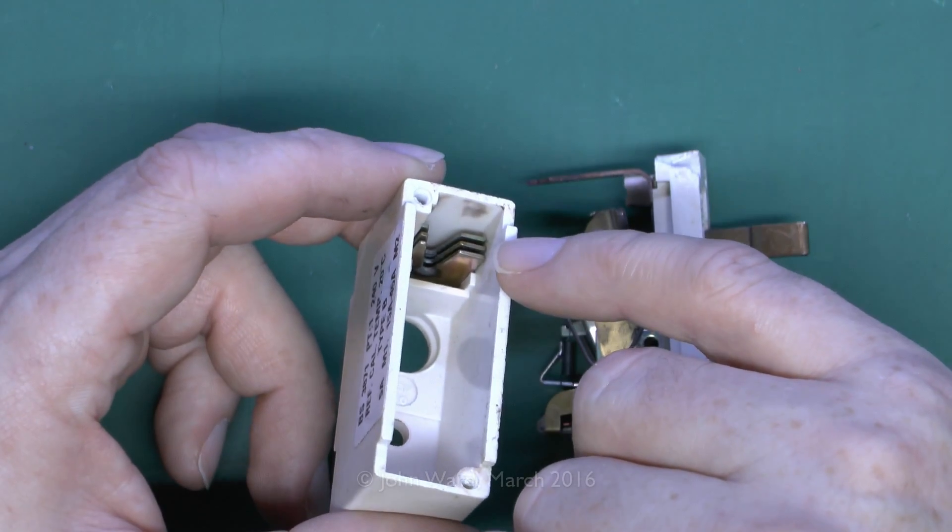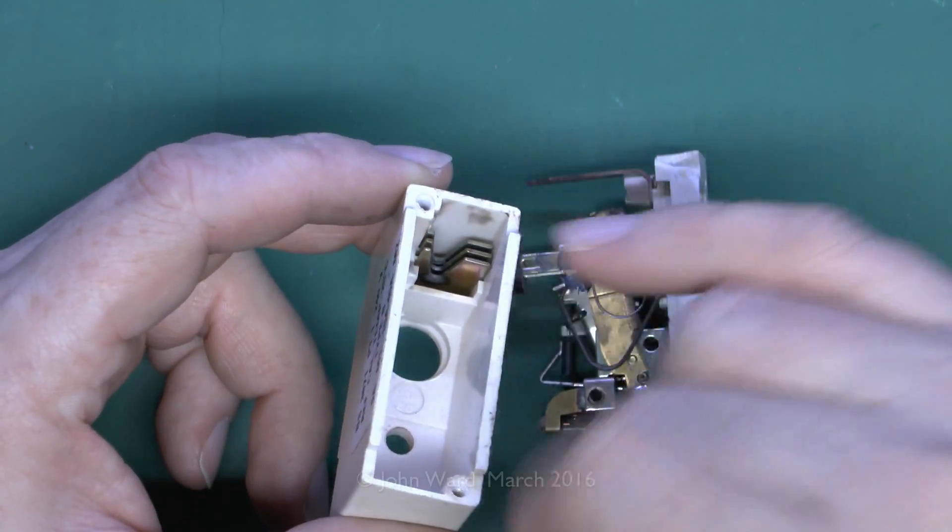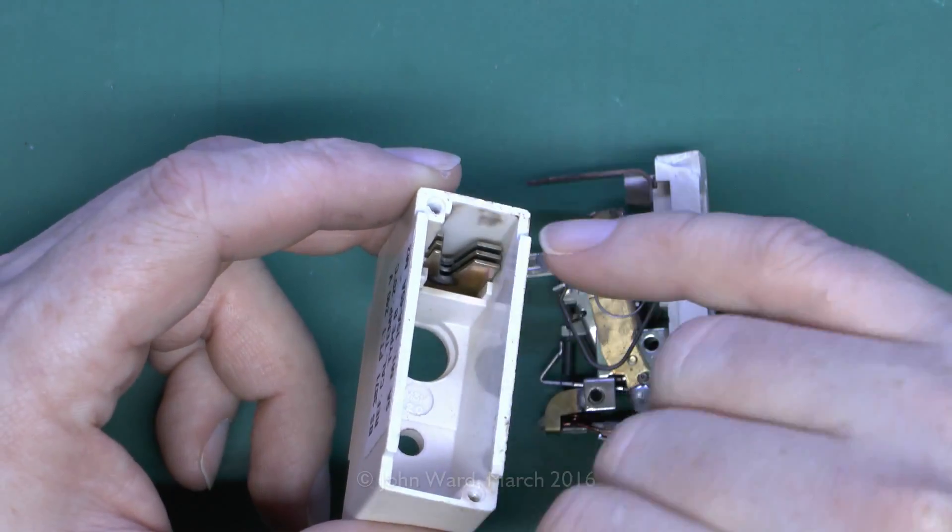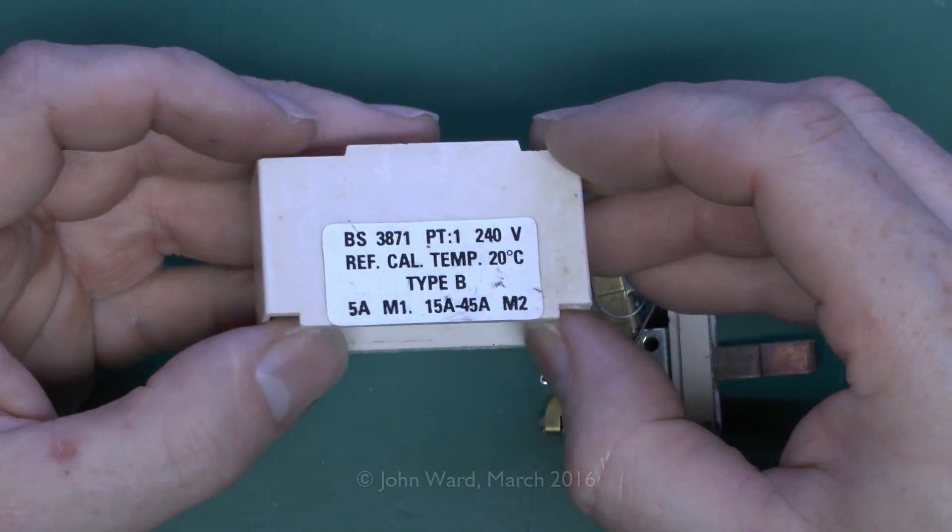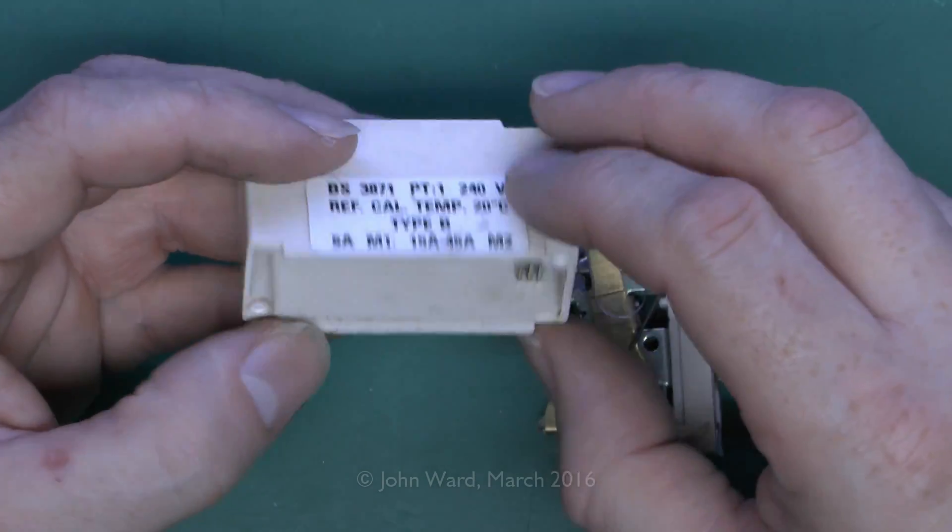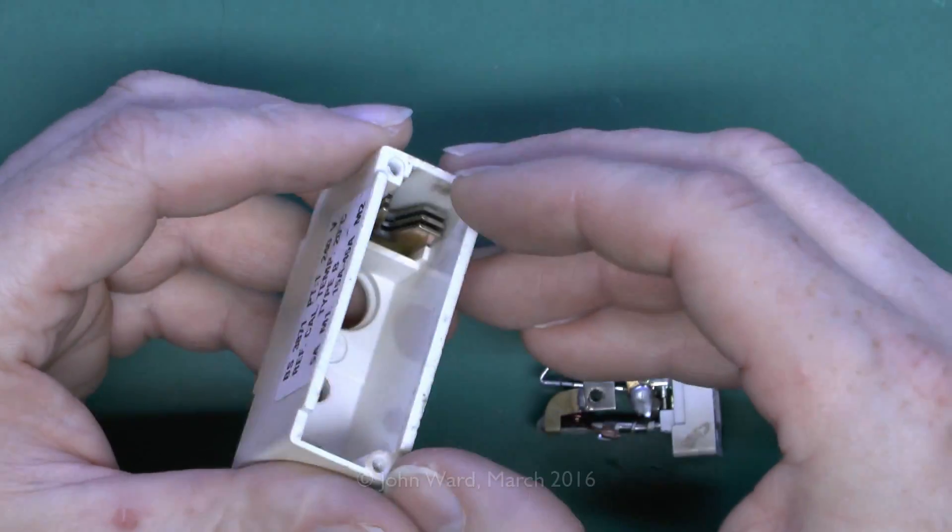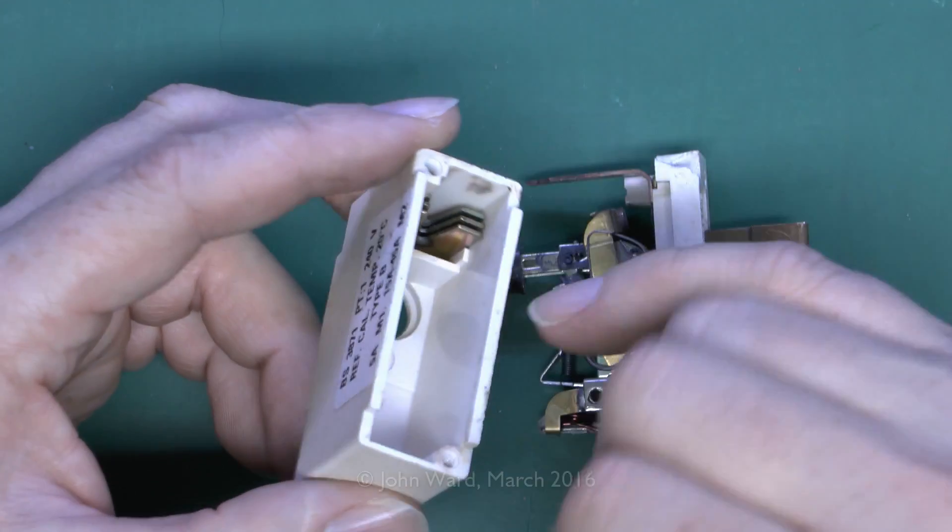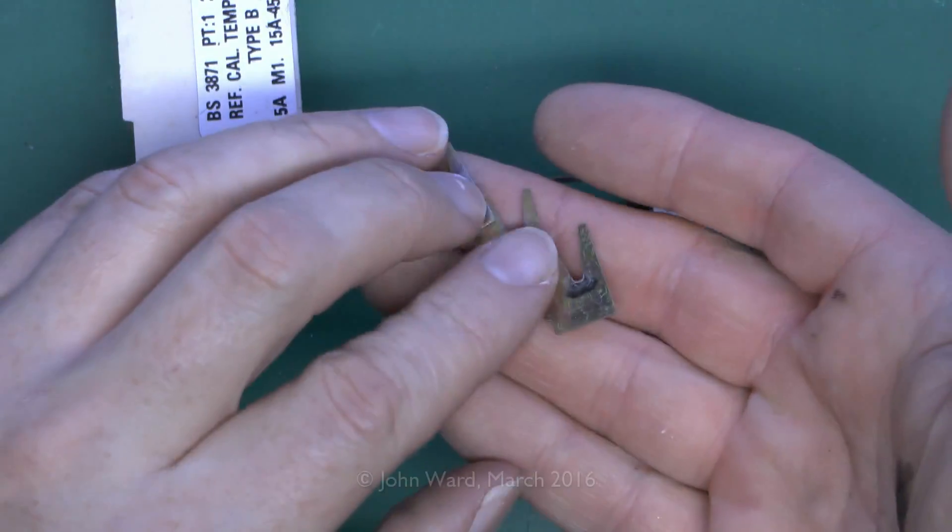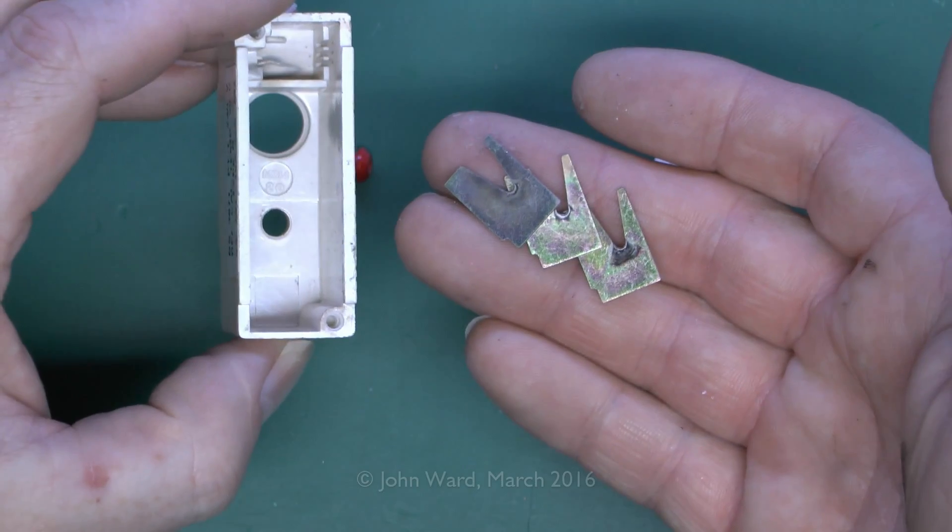In a previous video we opened a more modern circuit breaker. There was a whole big rack of them, sort of an inch or so wide. But here we've only got those three. And this really highlights one issue with these circuit breakers in that their breaking capacity is actually fairly low, considerably lower than modern ones would be. But I say it's got the three plates in the top there, and those are basically just pieces of steel just slotted in the top there.